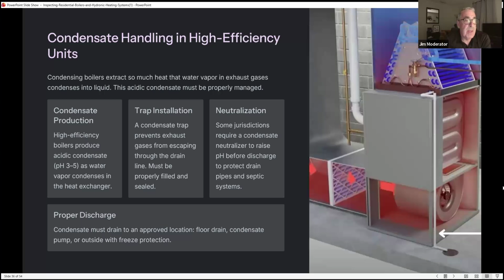Handling high efficiency units. Condensing boilers extract so much heat that water vapor in exhaust gases condense into a liquid. This acidic condensate must be properly managed. Condensate production: high efficiency boilers produce acidic condensate, 3 to 5 pH, as water vapor condenses in the heat exchangers. Trap installation: a condensate trap prevents exhaust gases from escaping through the drain. It must be properly filled and sealed. Neutralization: some jurisdictions require a condensate neutralizer to raise the pH before discharge to protect the drain pipes and septic systems.